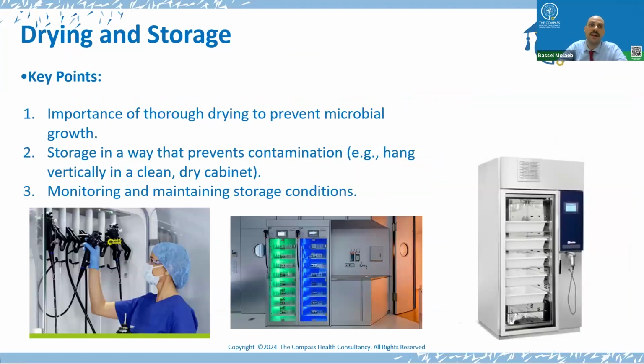So next comes the drying and storage. Those constitute the final steps in the reprocessing. So drying greatly reduces the possibility of recontamination of the endoscope by waterborne microorganisms. Drying must be performed even if the AER has a purge or a drying cycle. You need to conduct a risk assessment to decide if alcohol is to be used after that cycle.